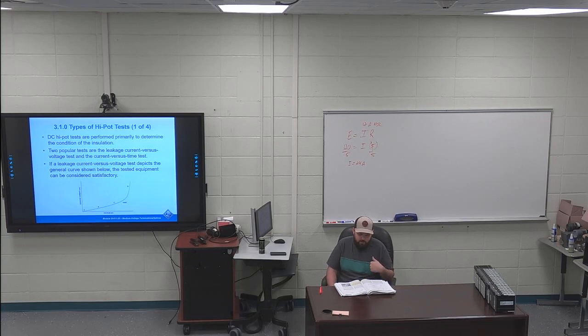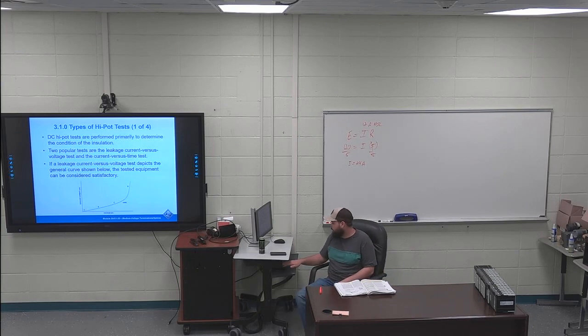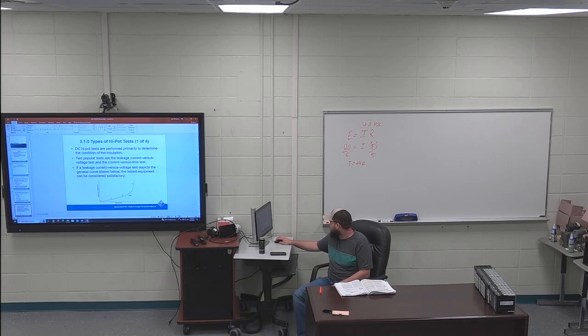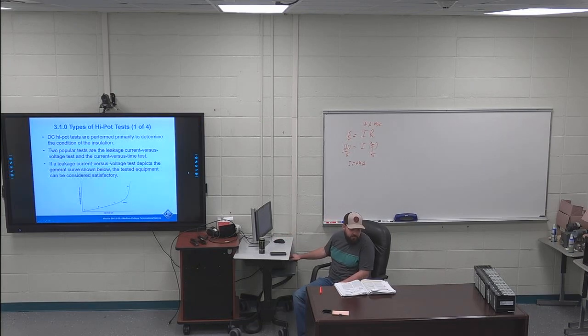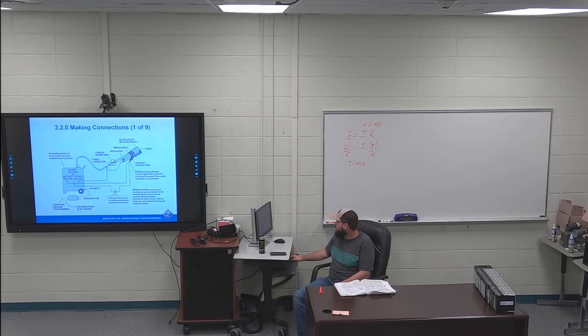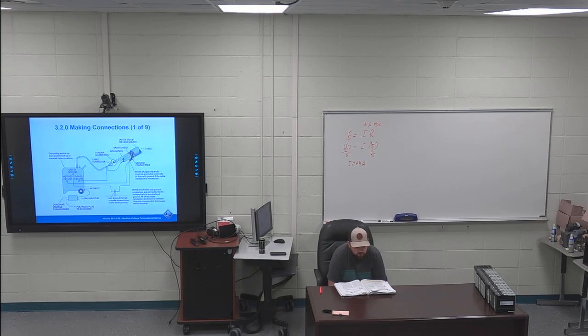They go through and talk more about that and how they're doing these tests. I don't have any highlights in 32 and 33. 3.2.0 goes into making connections, making your connections for doing a hi-pot test. Sorry. But if you go on to page 34, they go through the steps of this. I have step 7 highlighted. So step 7 is plug the line cord into a 120 volt 60 hertz single phase outlet and clip the ground wire coming from the line cord to the conduit receptacle mounting screw or another ground source.